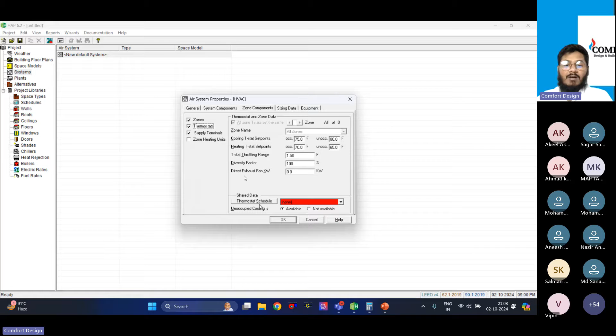Next we have the plant. We just have to choose the plant type, which doesn't impact the heat load calculation since we're already done with that. This is a new addition, choosing the plant room type, like chiller plant room, changeover plant room, or heat recovery plant room, which weren't in the initial HAP. So let me go with the generic chilled water plant room.